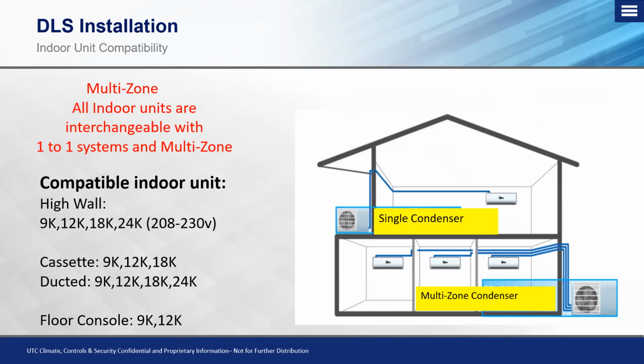So on multi-zone units, the nice part is that our single zone and multi-zone systems are all interchangeable. So that means that indoor units are not just proprietary to a single zone system, they will also work on our multi-zone system, whether it's an entry tier, a mid-tier, or a high-tier high-wall unit. They are all interchangeable on the multi-zone system. Now, the single zone setups have their own proprietary, such as the 40 MHH is only compatible with an entry tier outdoor unit. The 40 MAQ is only compatible with a single zone outdoor unit, such as the 38 MAQ. But the 40 MHH, the 40 MAQ, and the 40 MPH, which are all three different tiers of high wall units, low, medium, and high, can all be put on the multi-zone outdoor unit. So they are interchangeable on the multi-zones only.